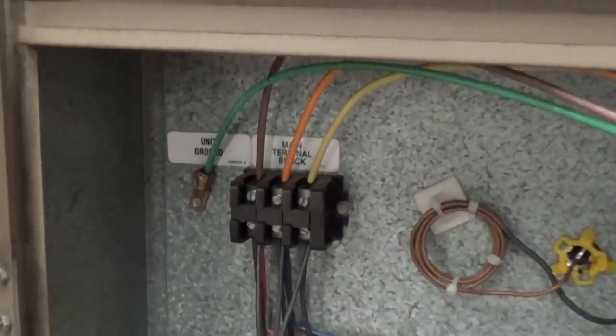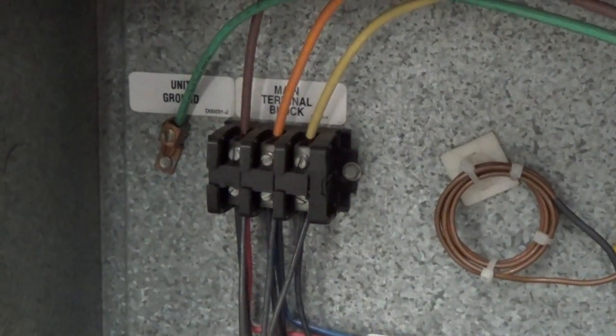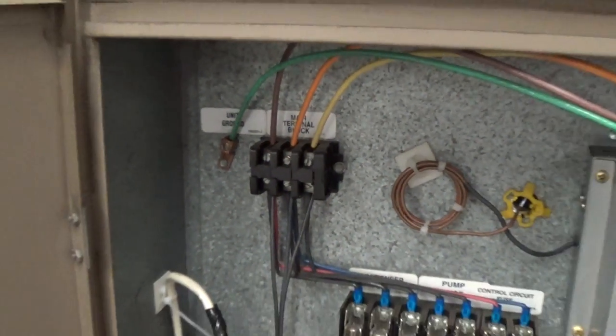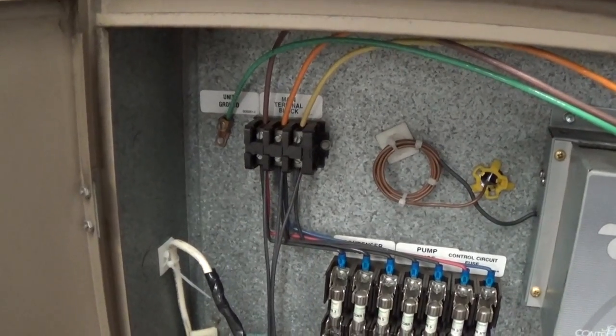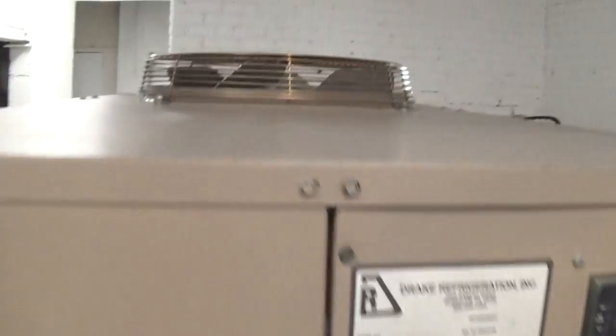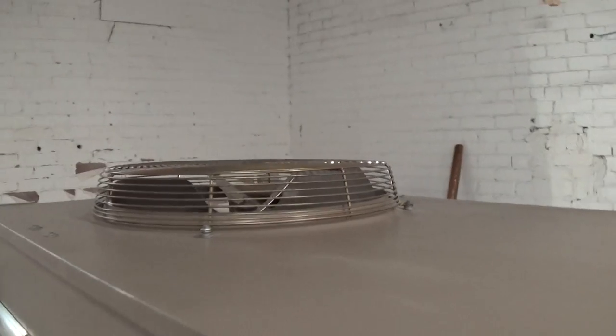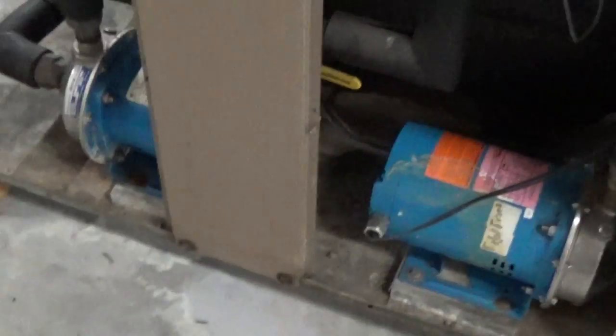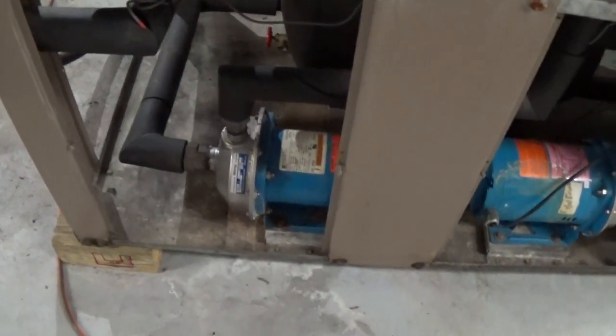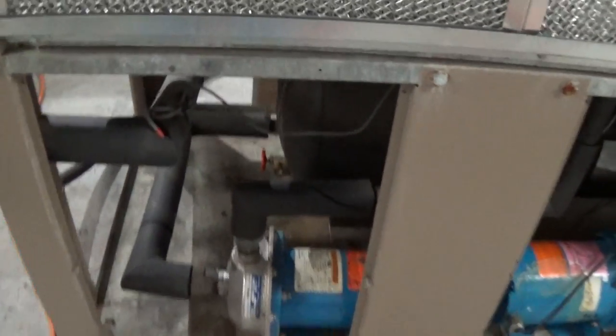Your main incoming power is going to come here. It is 460 volt three phase. It is rotation dependent. So in this case here, the condenser fan is single phase, and we have two pumps. We have the recirculation pump, which draws off our insulated reservoir tank and then comes back up. There's a shut off here too, which comes back up through the body to our heat exchanger.